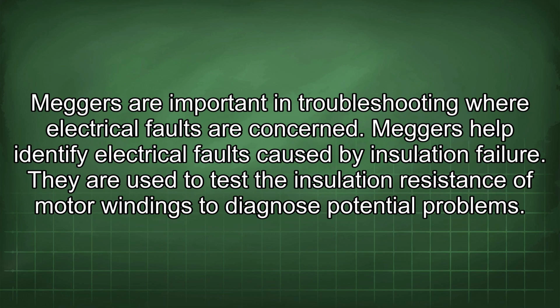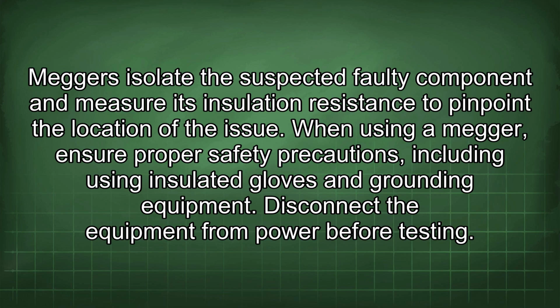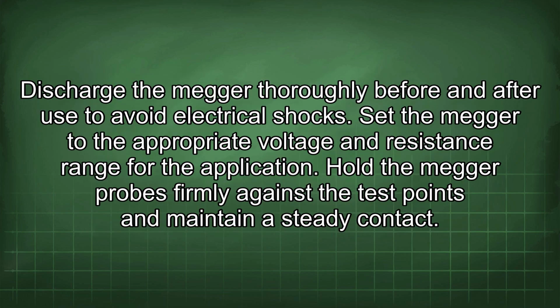Meggers are important in troubleshooting where electrical faults are concerned. Meggers help identify electrical faults caused by insulation failure. They are used to test the insulation resistance of motor windings to diagnose potential problems. Meggers isolate the suspected faulty component and measure its insulation resistance to pinpoint the location of the issue. When using a Megger, ensure proper safety precautions, including using insulated gloves and grounding equipment. Disconnect the equipment from power before testing. Discharge the Megger thoroughly before and after use to avoid electrical shocks.